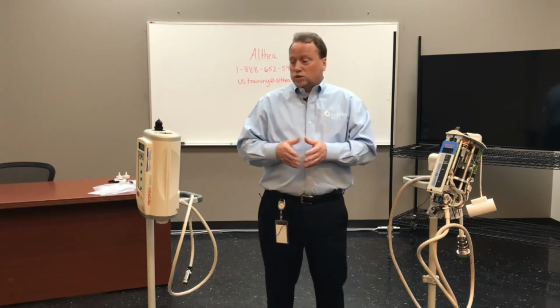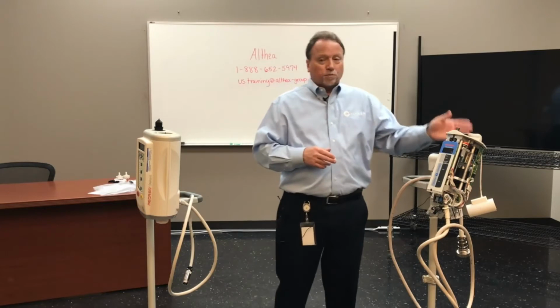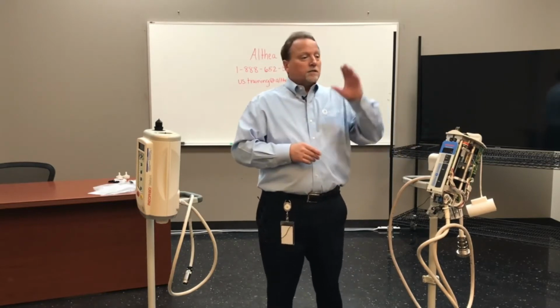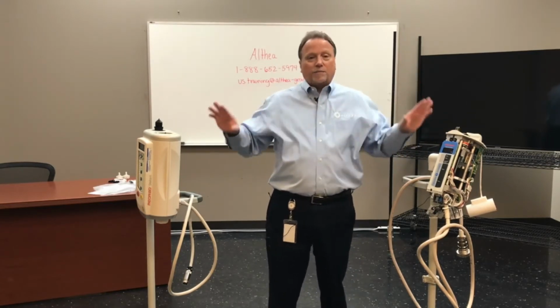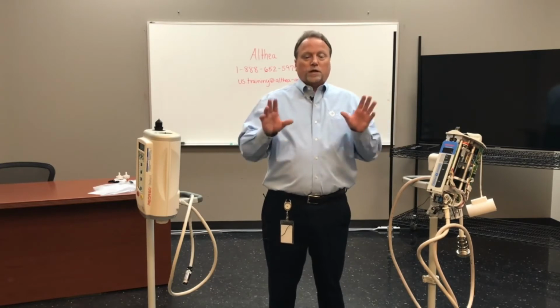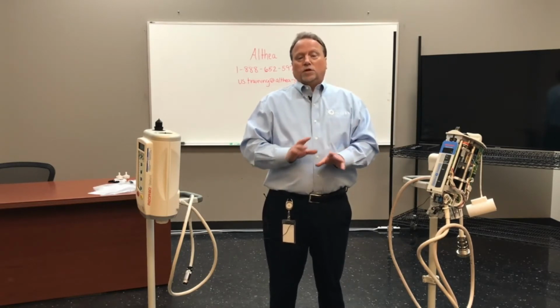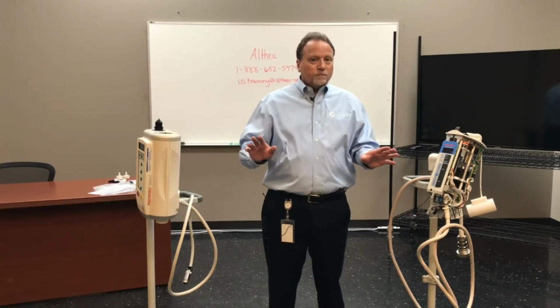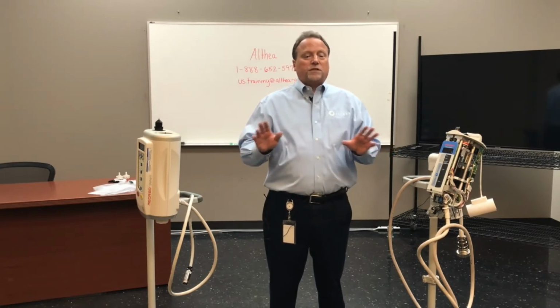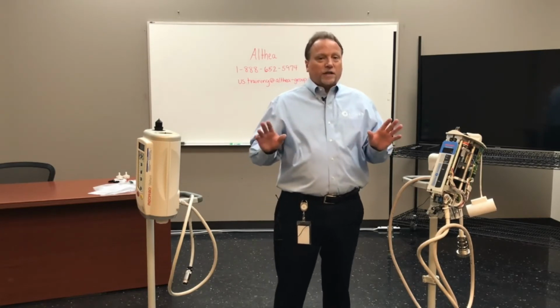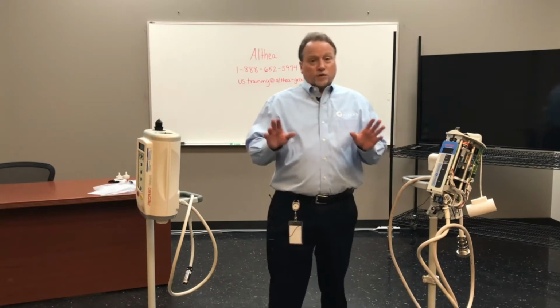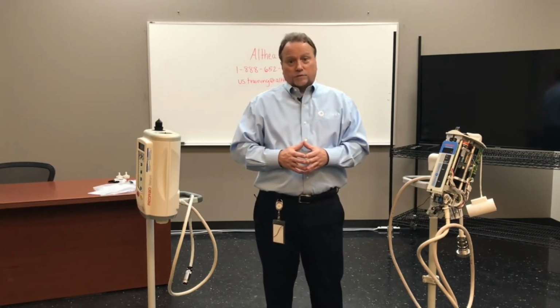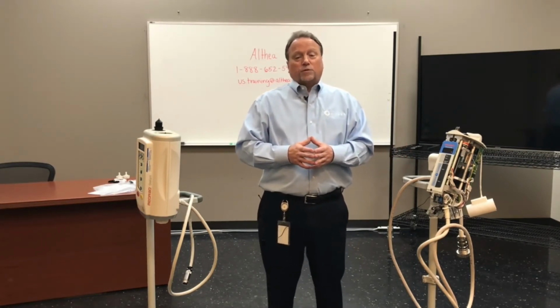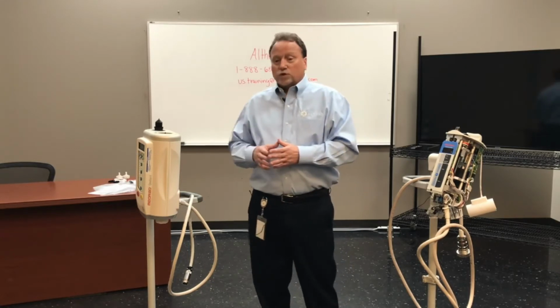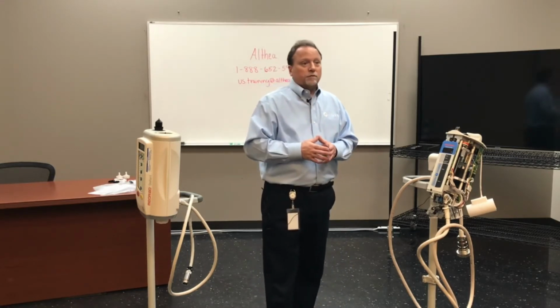So keep that in mind. Run your test injection, whether it be on a Stellant, a Provis, a CTA, or CVI, it doesn't matter. Run a test injection. You don't need water, you just need to run it through its paces to make sure you don't get any errors. And if you do get errors, they're probably going to be intermittent errors. That's going to be the trouble with resolving that problem. But maybe you can. Maybe you can.